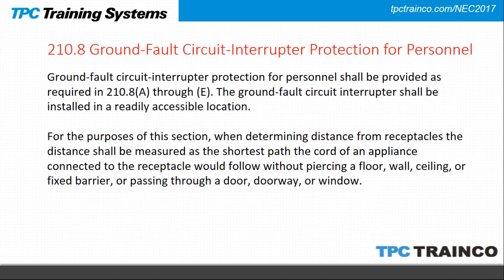Section 210.8 addresses GFCI protection for personnel and clarifies how to measure distances for GFCI requirements. The GFCI outlet must be readily accessible. For determining the distance from receptacles, the distance shall be measured along the path of the cord. For example, a receptacle under a sink for a garbage disposal — you measure how that cord would travel its path to determine if it is within six feet of the sink and therefore requires GFCI protection.